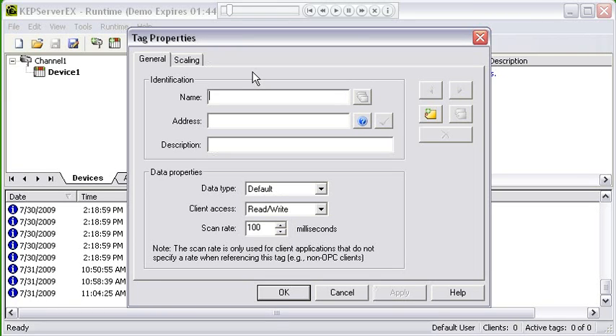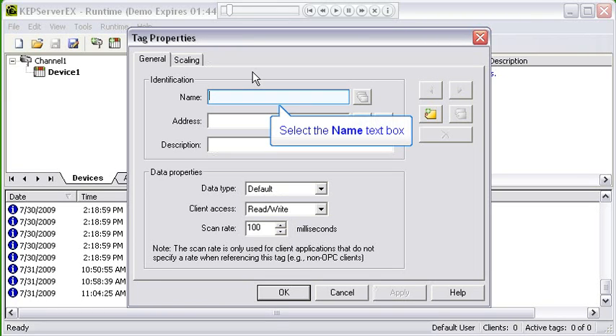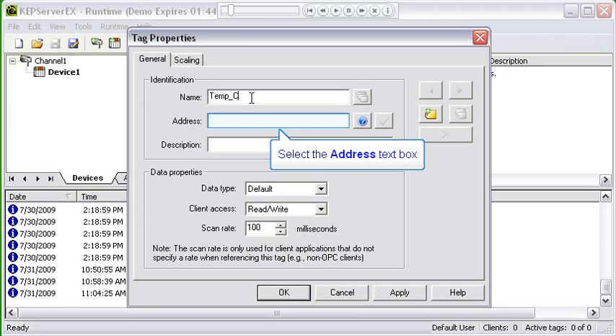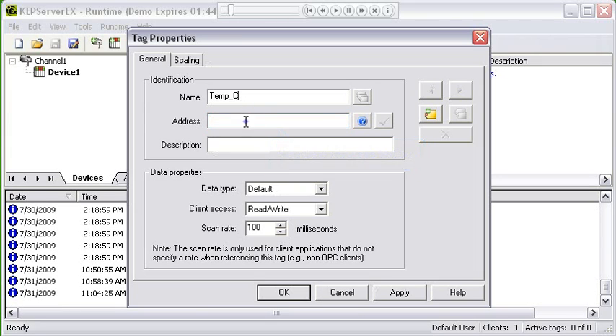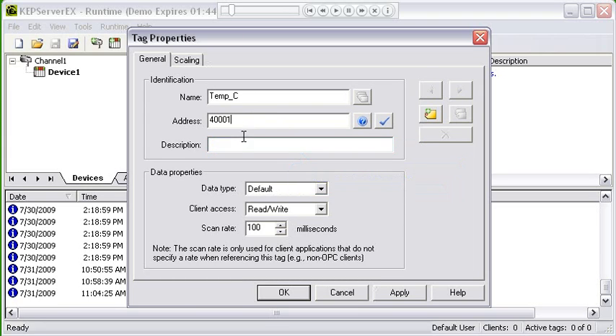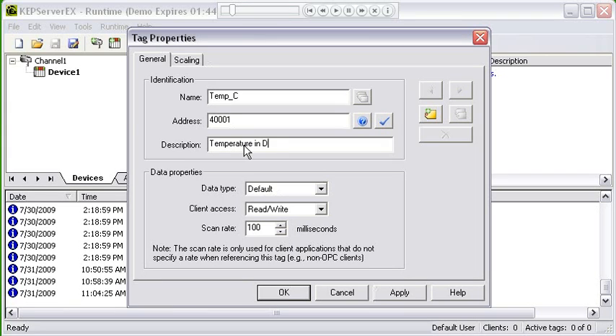The tag property window opens up. First thing we're going to do is create the tag name. This is my temperature tag and I'm going to call it temp_C. It's at Modbus holding register 1, and I'm going to give it a description: Temperature in degrees C.